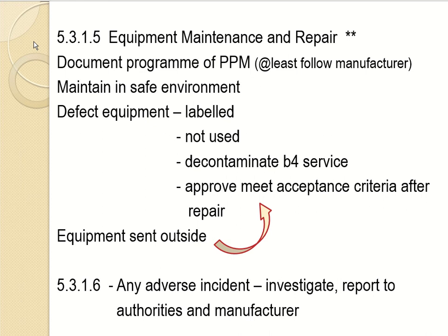Okay, next under clause 5.3.1.5, equipment maintenance and repair, there should be a documented program for periodic preventive maintenance, which at least follows the manufacturer requirement. The equipment should be maintained in a safe environment. The defective equipment should be labeled, not to be used, decontaminated before service, and after the repair should meet the acceptance criteria before being approved. And same also with the equipment that is sent outside, it should be approved to meet acceptance criteria. And under clause 5.3.1.6, any adverse incidents should be investigated, and reported to authorities and manufacturer.